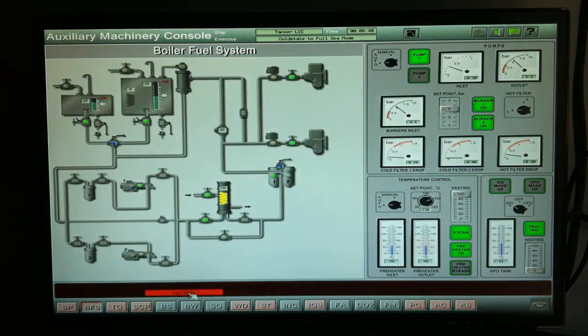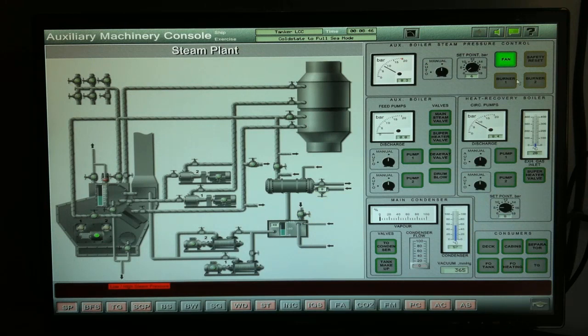Okay, so we have an alarm of the fuel temp. Okay, so I believe fuel is already now circulating. We could now fire the boiler. Fire the burners 1 and 2, set to auto. By the way, you need to adjust the pressure settings to around 15 bars so that the burner will automatically fire and raise steam. So once you have fired the boiler, you could now start the feed pump. Put it on auto. Open superheater valves. Start pump 1. Put it on auto on the heat recovery boiler.